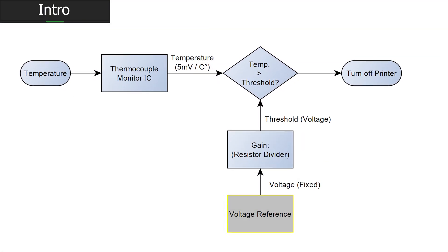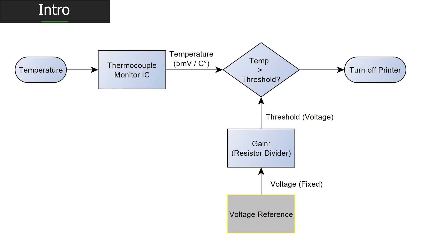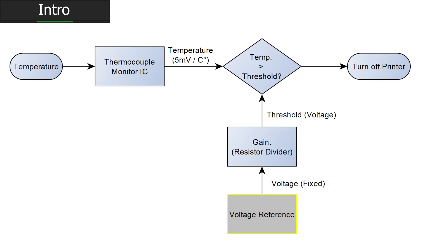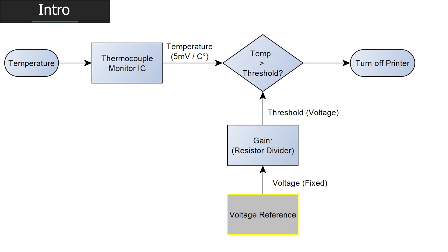Seth, our temperature monitor can only be as accurate as its reference. If the thermocouple is perfect, the comparators are perfect, but the reference itself isn't perfect, this becomes a 1-to-1 error in the measured temperature.